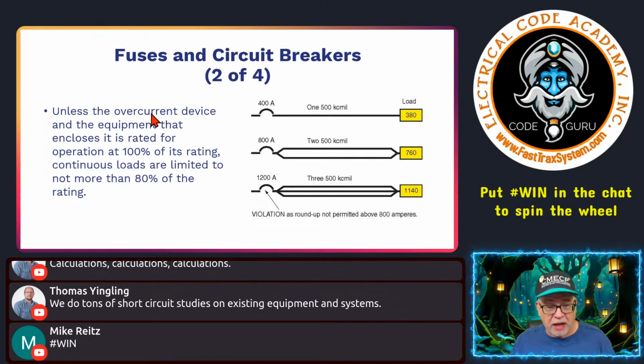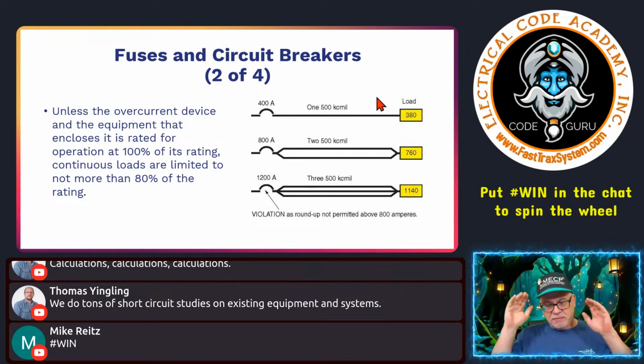But if we're following the next size up rule and everything applies, then this is an example. But what you'll notice is that this conductor of 500 kcmil copper, always assume copper unless stated otherwise, is only good for a certain amps. So since an overcurrent device doesn't correspond, then it can be terminated on a 400. Well, as long as the conductor is sized to handle the load, no harm, no foul.